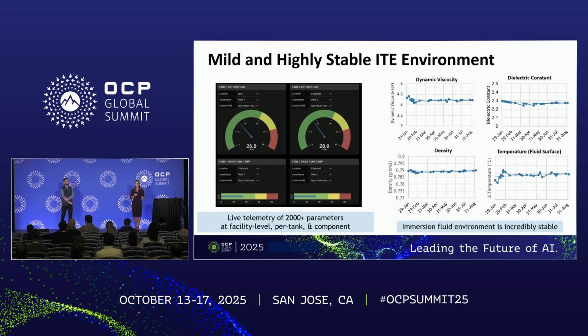The other thing that holds people back from adopting immersion is not really understanding the thermal environment and the benefits you get from a hardware and component perspective. We have over 2,000 parameters that we're measuring in live telemetry. We operate our data center with a very high degree of professionalism, so this telemetry allows us functional controls, safety controls, safeguards, and operational controls. We're able to set limits to meter and think through things like proactive service and maintenance.